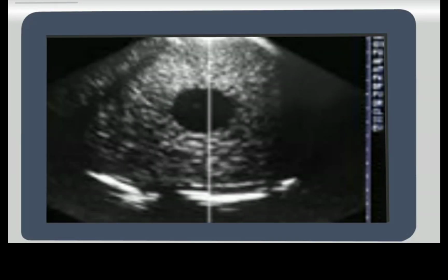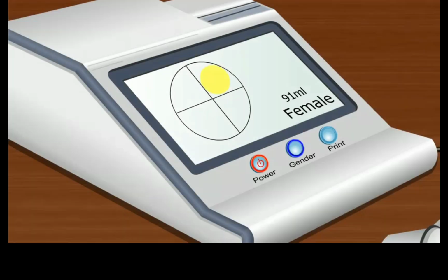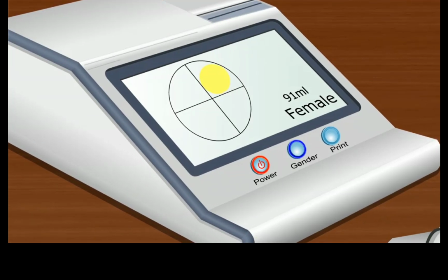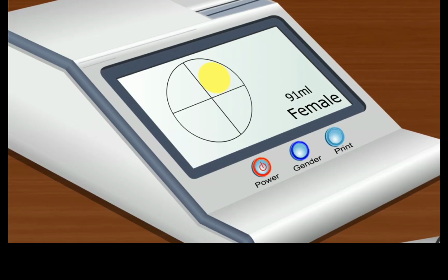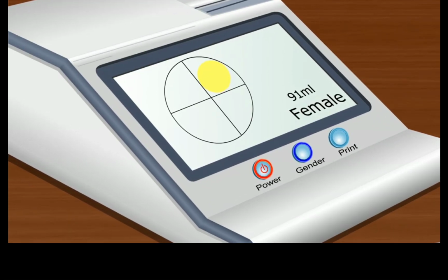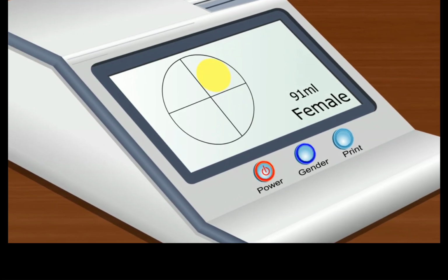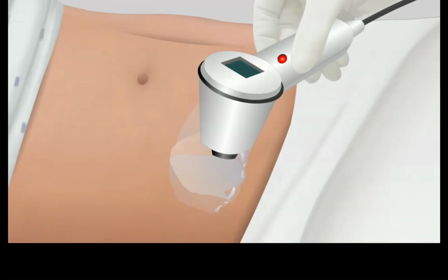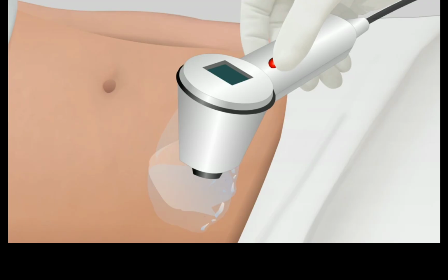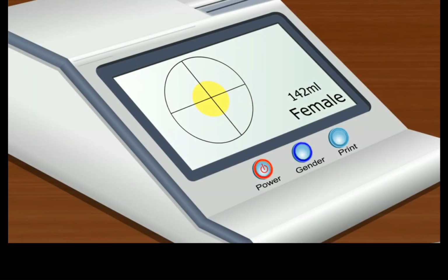If the scanner includes a pre-scan mode that allows location of the bladder in a real-time view, make sure the bladder is centered within the image. If the scanner does not include a pre-scan mode and the edge of the bladder overlaps the side of the crosshairs, or if the bladder is not centered within the ultrasound image, the measured volume will be inaccurate, falsely low. Readjust the probe position and rescan until the bladder is properly centered on the aiming screen. Repeat the scan to obtain an accurate measurement.